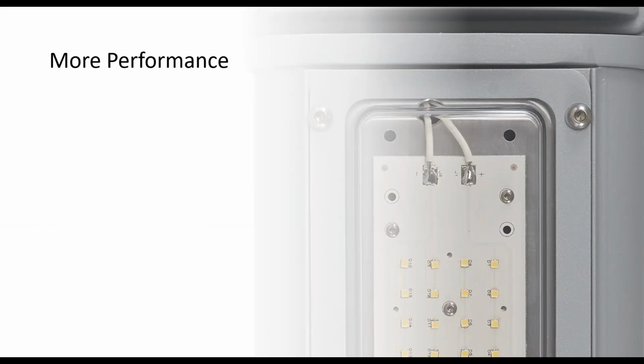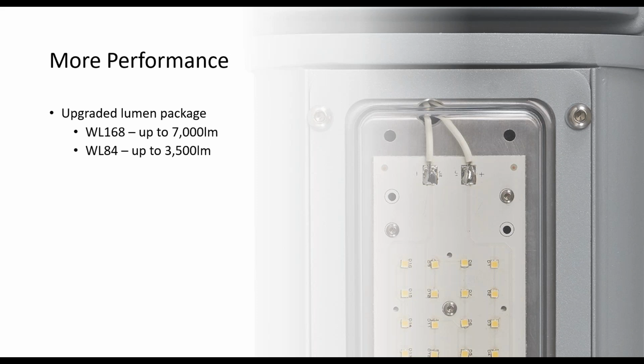Moving on now to the performance. So another big driver behind this project has been to maximise performance from the new linear. We've addressed that on 2 fronts. One was to get more power out of the luminaire itself. So we now have the WL168 variant, which would be a traditional 2x36 watt fluorescent replacement. That's now providing up to 7,000 lumens. And the WL84 variant, so your traditional 2x18 watt fluorescent replacement, providing up to 3,500 lumens.